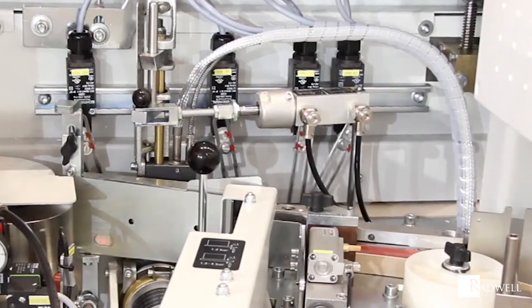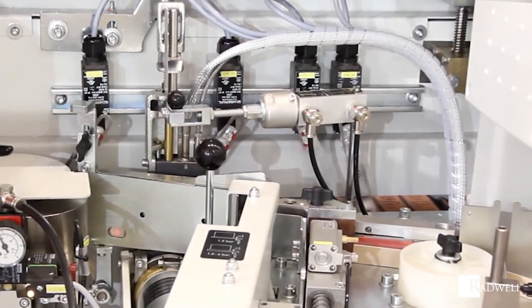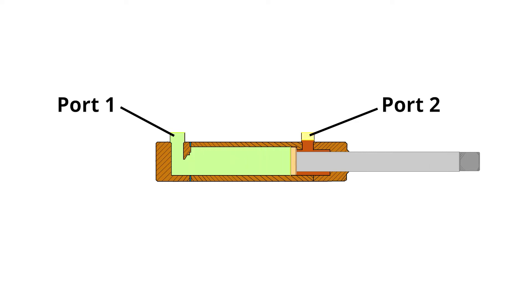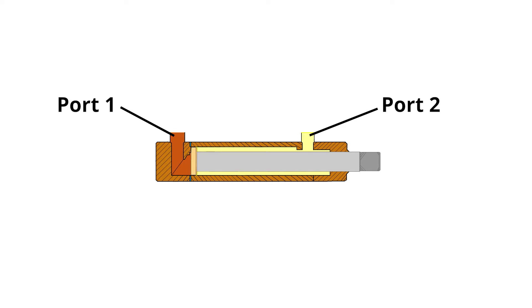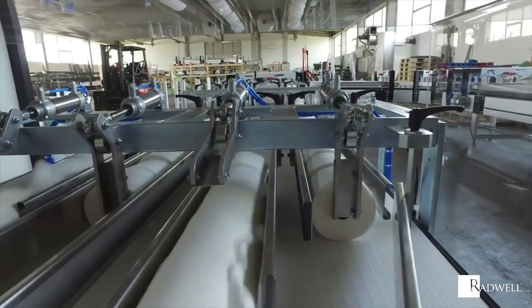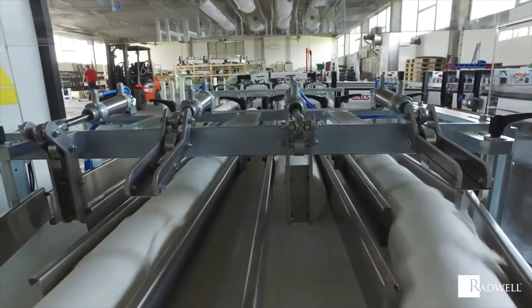A double acting cylinder's working principle is to transfer force in two directions to provide a back-and-forth motion. Double acting cylinders have a port on each side of the cylinder. A pressurized force enters the port at one end to push the piston forward, then pressurized force enters the second port to retract the piston back. Double acting cylinders are mostly used for applications to open and close or pick and place.